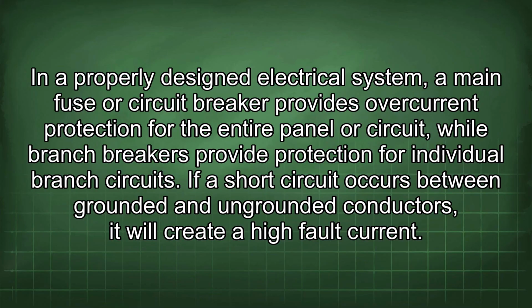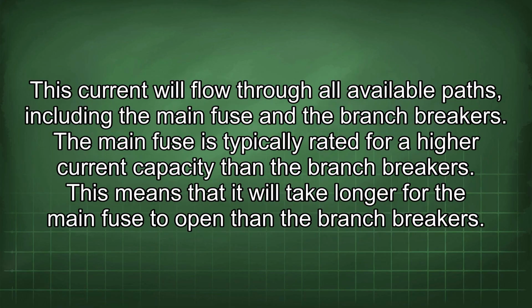In a properly designed electrical system, a main fuse or circuit breaker provides overcurrent protection for the entire panel or circuit, while branch breakers provide protection for individual branch circuits. If a short circuit occurs between grounded and ungrounded conductors, it will create a high fault current. This current will flow through all available paths, including the main fuse and the branch breakers.